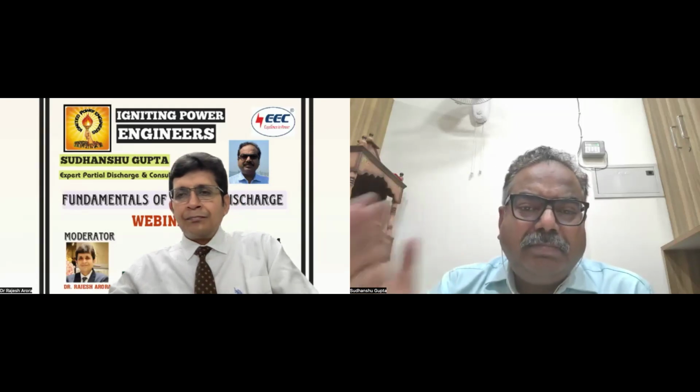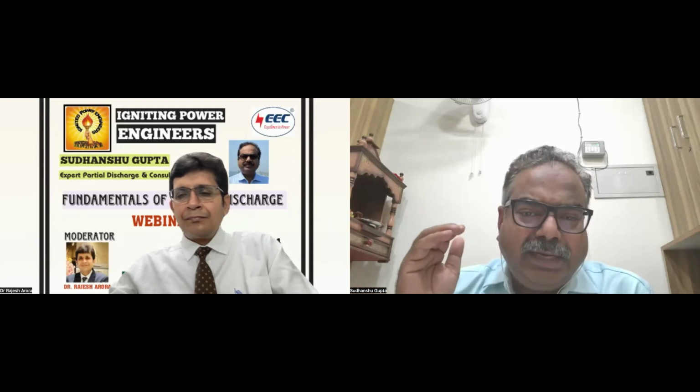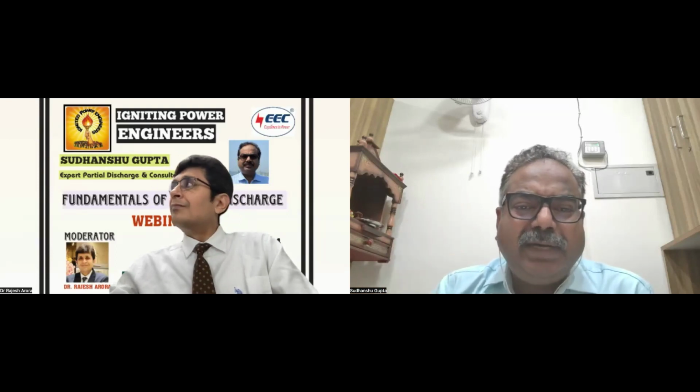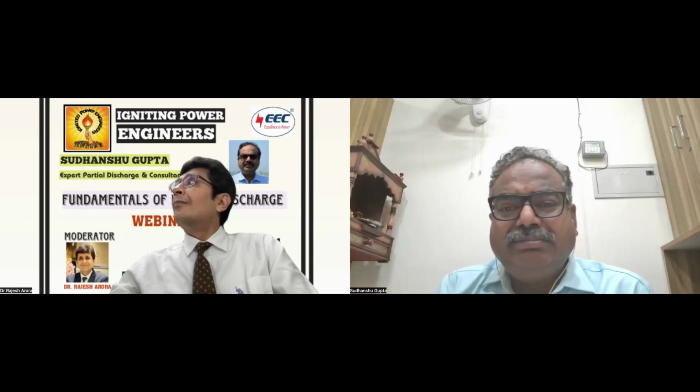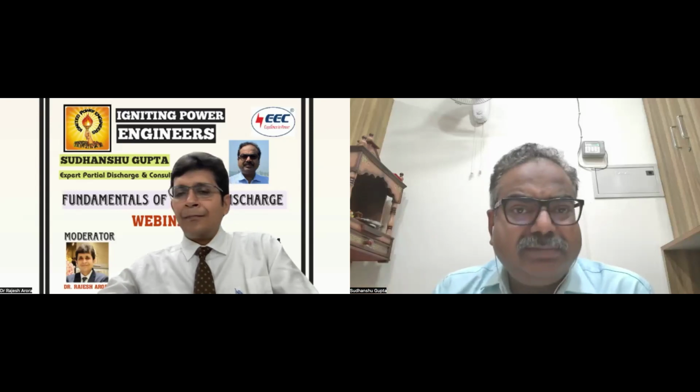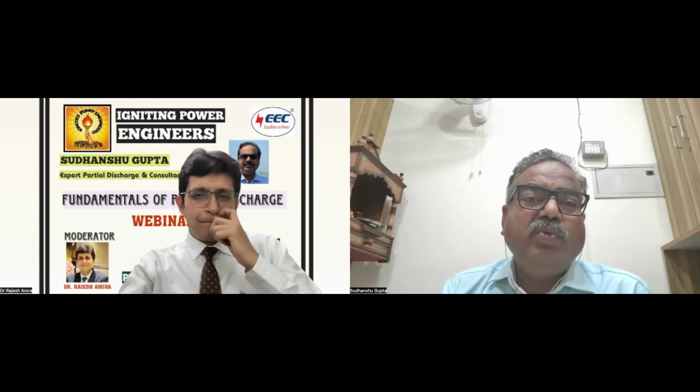Qualitrol pushed PD Tech to develop IEC 60270 equipment for field testing, and after many tests, they failed. I was the only one opposing it, saying don't waste your time on this equipment. I have done that kind of test a lot, and I know the difficulties.